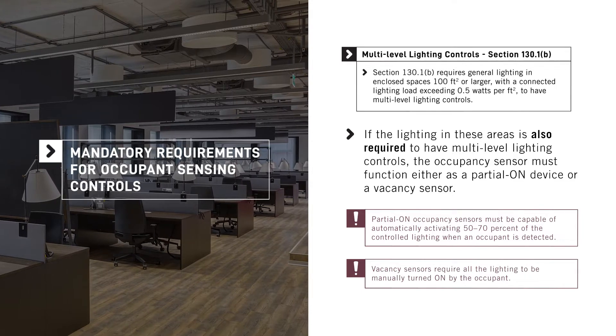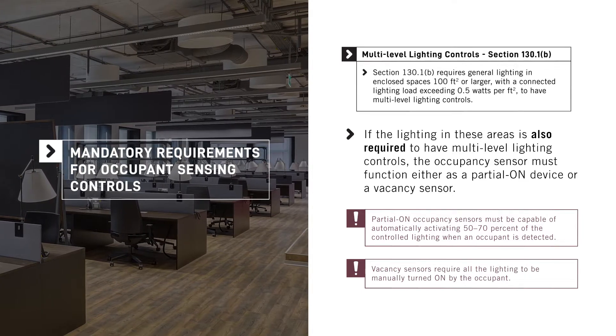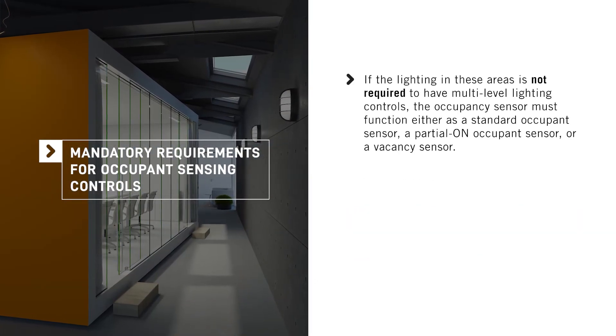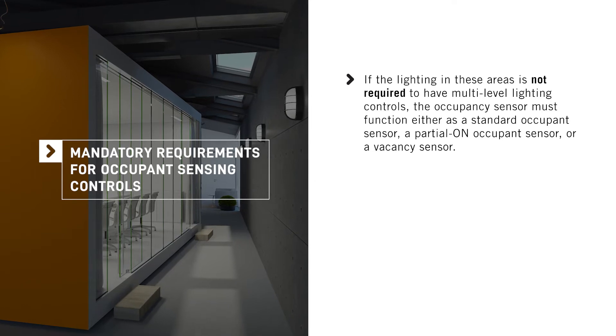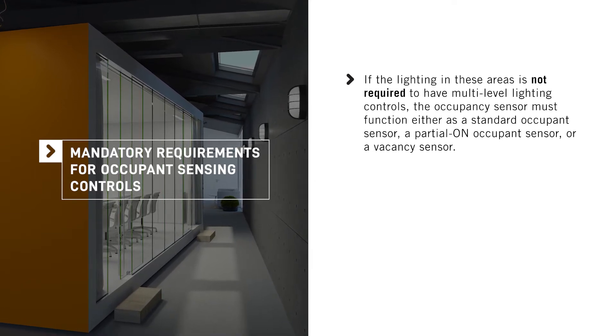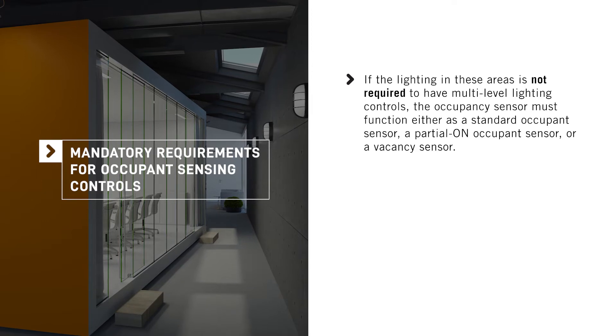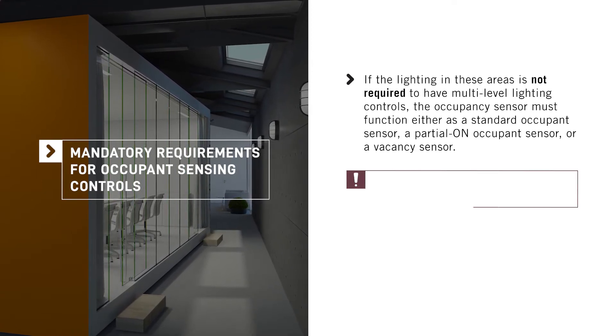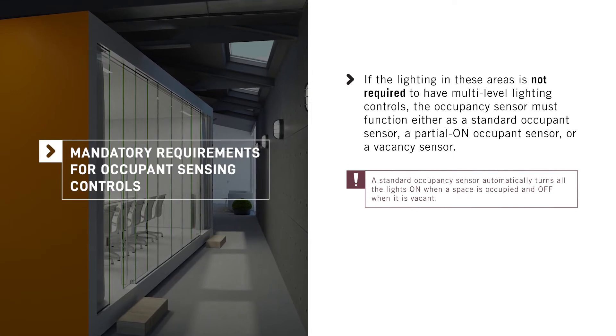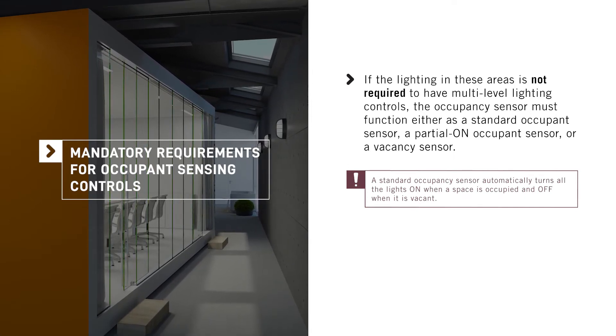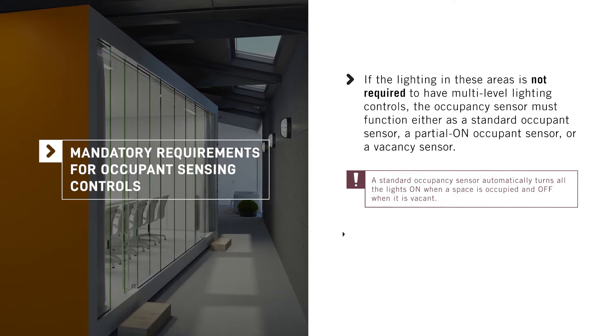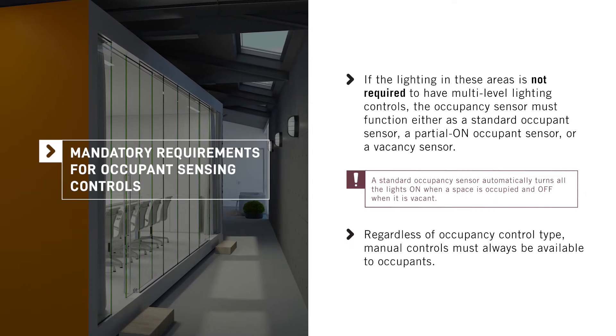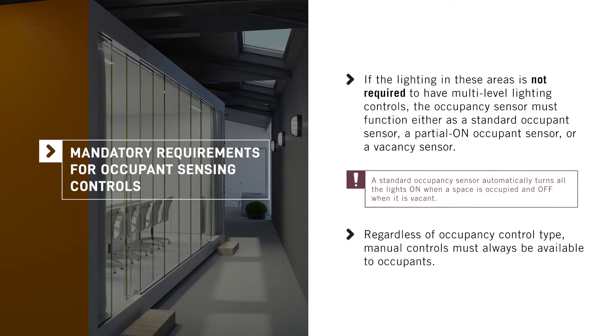Vacancy sensors require all the lighting be manually turned on by the occupant. If the lighting in these areas is not required to have multi-level lighting controls, the occupancy sensor must function either as a standard occupancy sensor, a partial-on occupancy sensor, or a vacancy sensor. A standard occupancy sensor automatically turns all the lights on when a space is occupied and off when it's vacant. Regardless of the occupancy control type, manual controls must always be available to occupants.